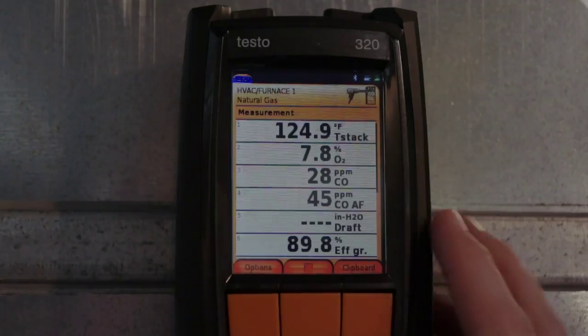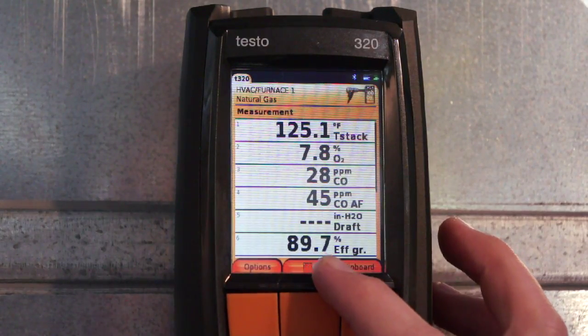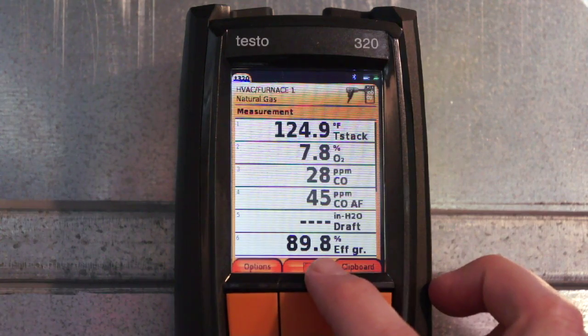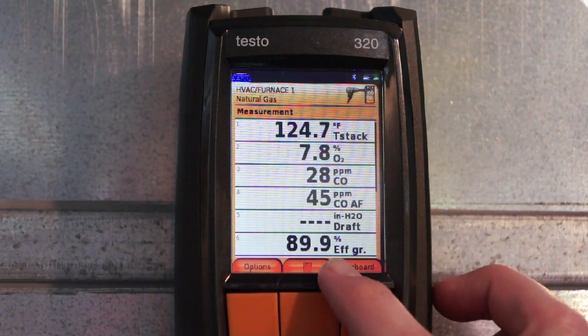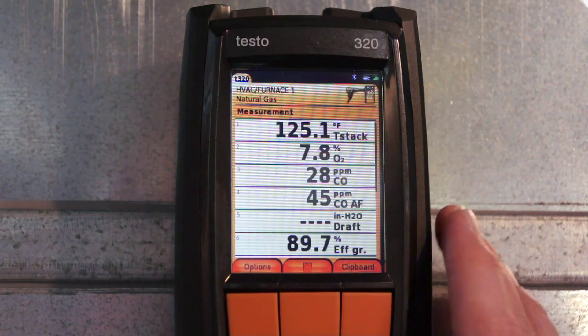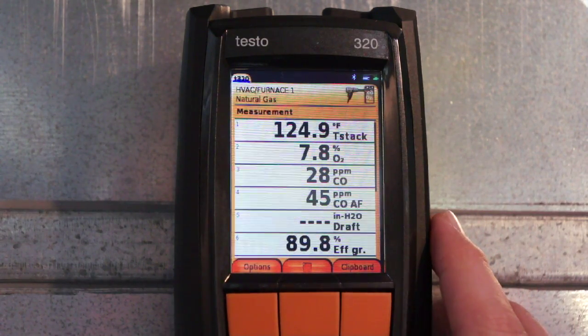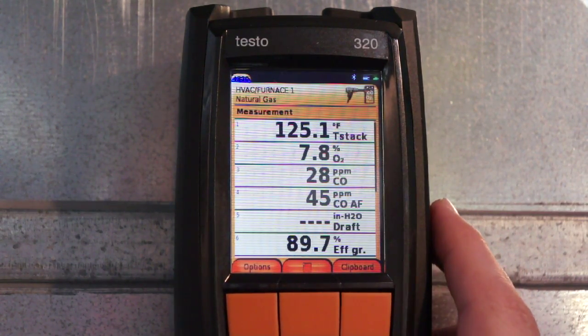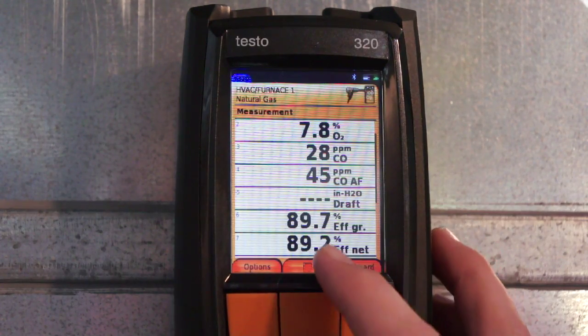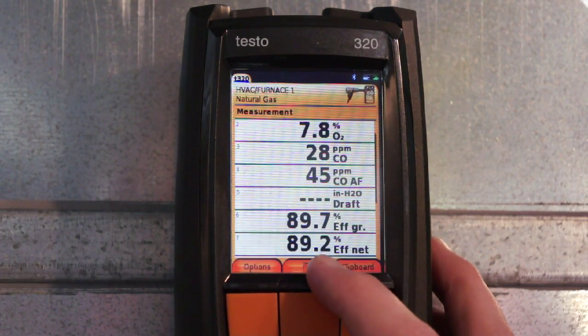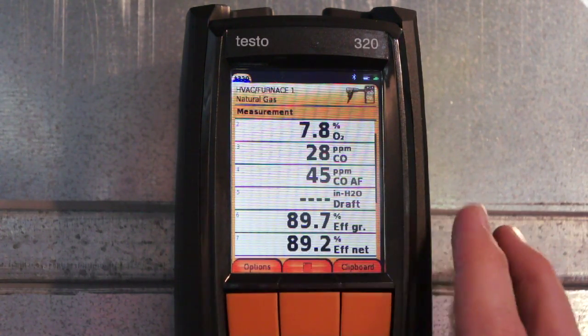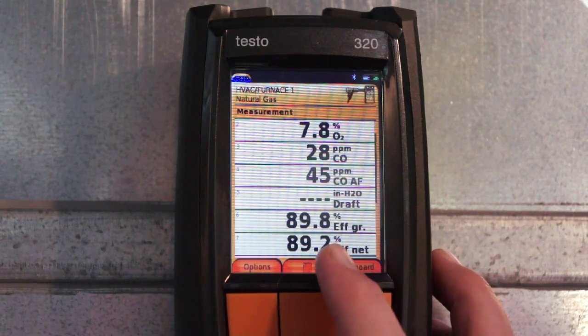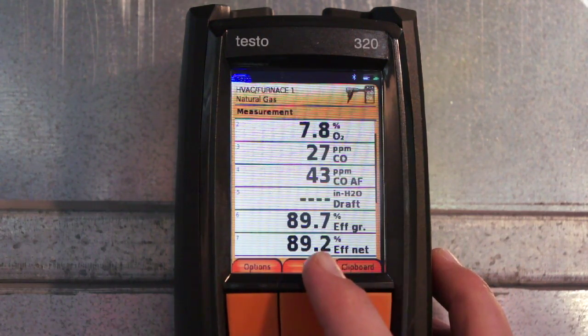If we take a look at the efficiency numbers now, you can see we're at about 89% efficient. This is a 90 plus furnace, and it is a true 90 plus. It's not a 95, so it's running right about where it should be. If I scroll down one, you'll see that I can see my gross efficiency and my net. Now, this furnace is a condensing furnace, but we are not very far into the condensing range at all.